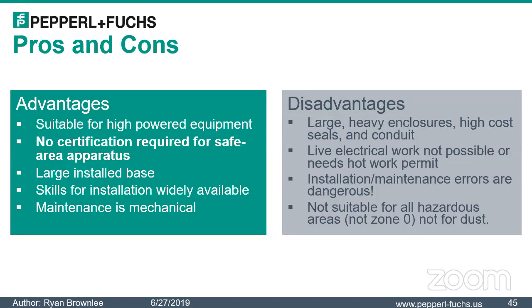Something to add to that, the most common thing that people mess up is with multi-conductor cables. They don't strip the cables, and you get an air gap between the cables going through. No two cables can touch. You can't have a gap anywhere. They have to be stripped. The worst thing is instrumentation. You deal with a whole bunch of little wires, and they'll use epoxy as opposed to a proper seal. It's got to be spotless. Otherwise, you have a path of propagation.